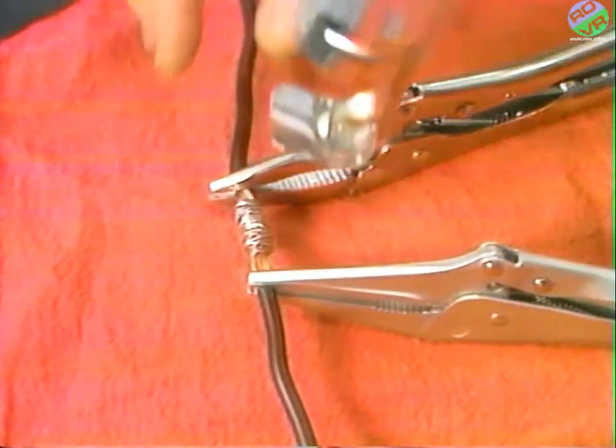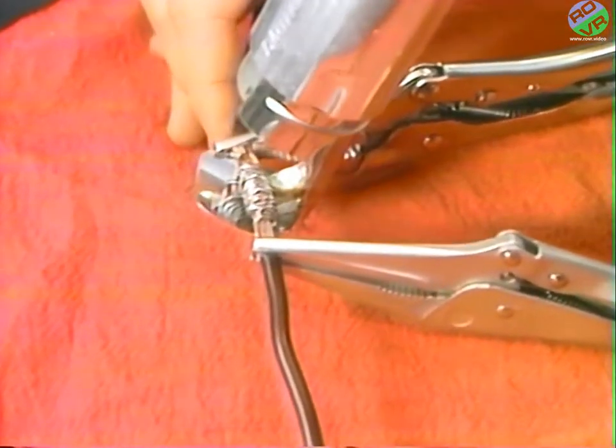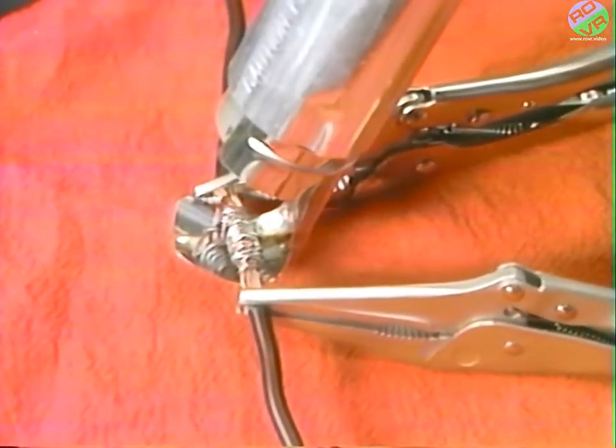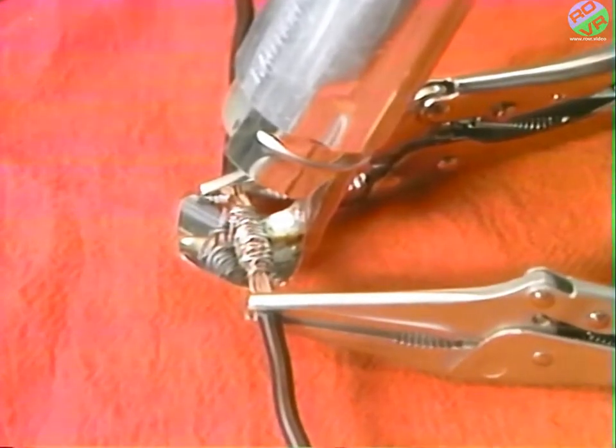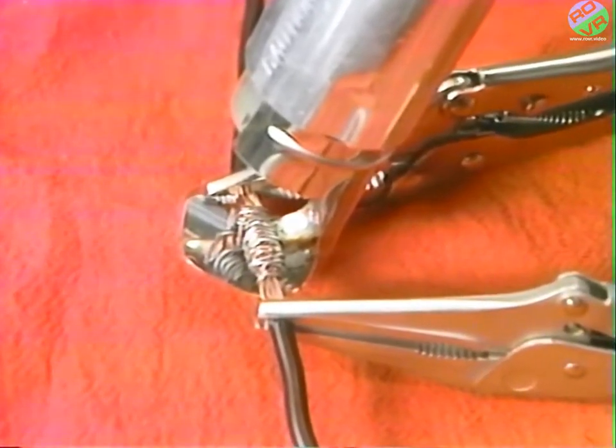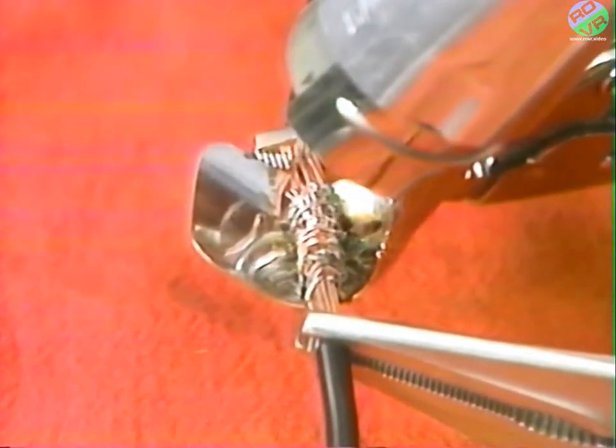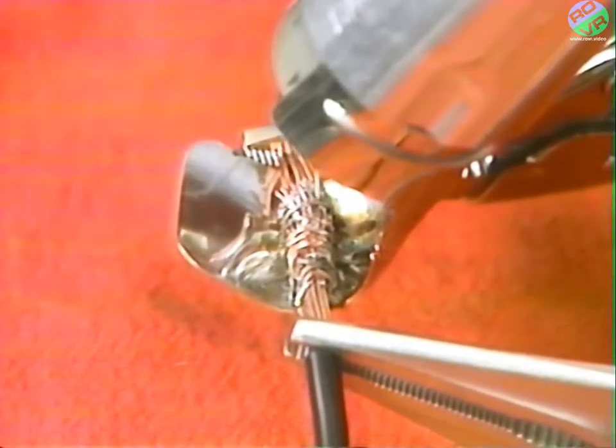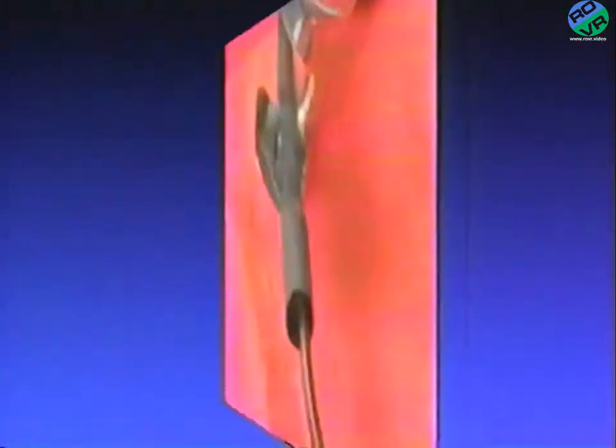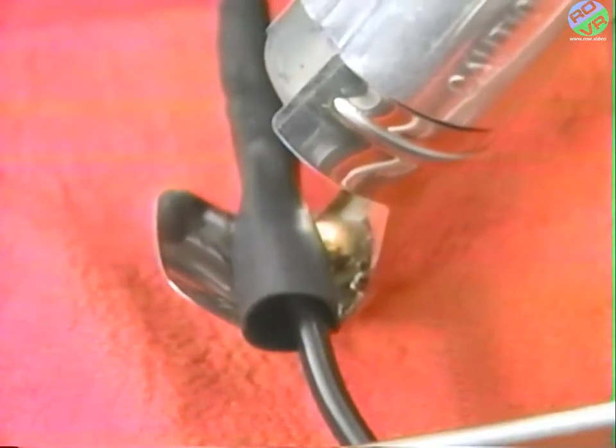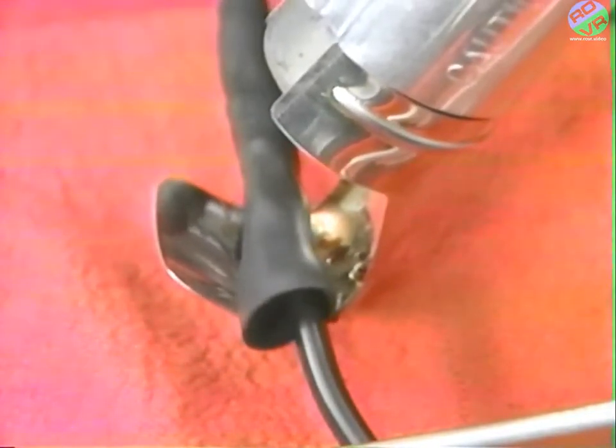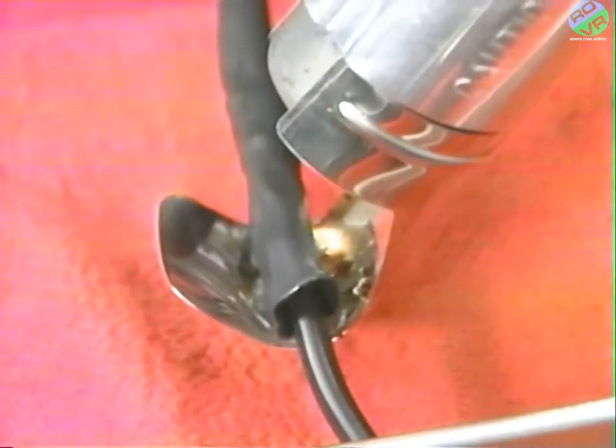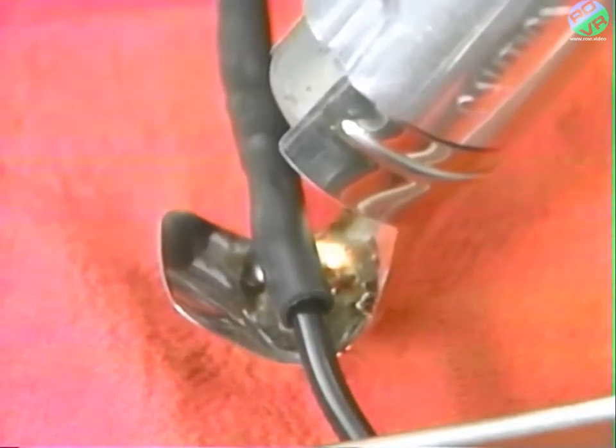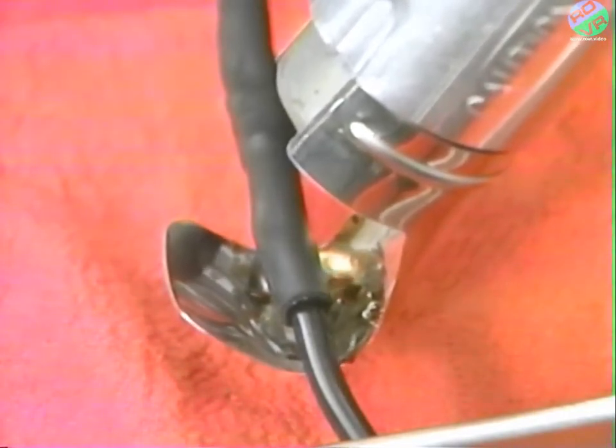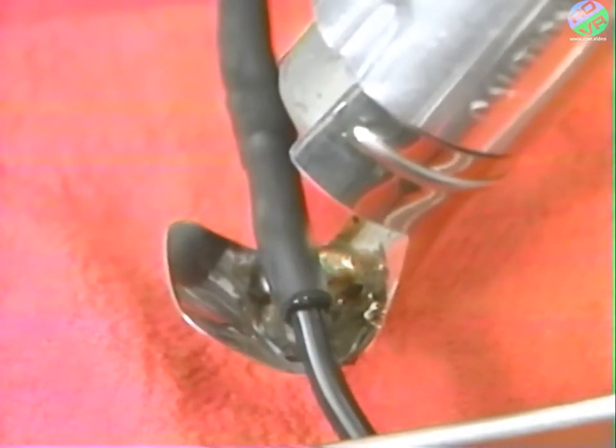Heat the joint with a 1500-watt heat gun rated at 700 degrees Fahrenheit. Use the heat gun's wraparound tip and lay the wire inside the tip with the heat gun vent closed. When the joint is heated, feed solder into the joint until it's filled and coated with solder. When the joint has cooled, center the shrink tubing over the joint and heat evenly until it shrinks tightly around the joint. This procedure can also be used to repair fuse links using the fuse link repair packages currently available.